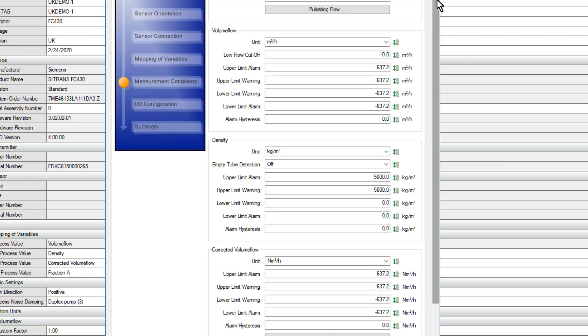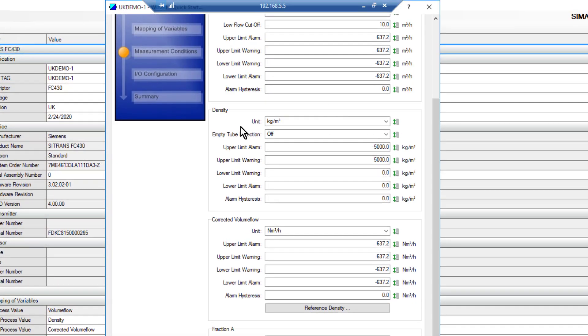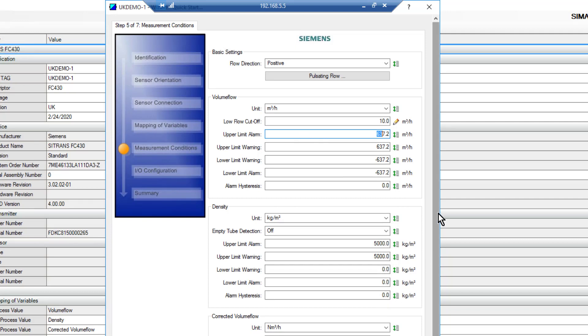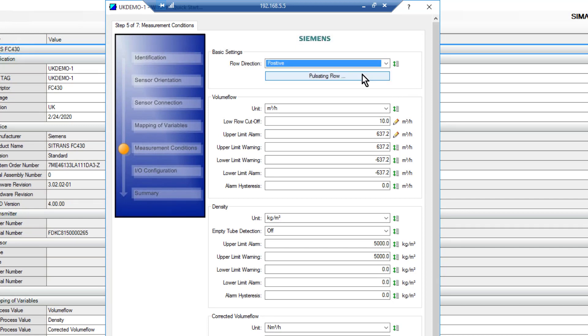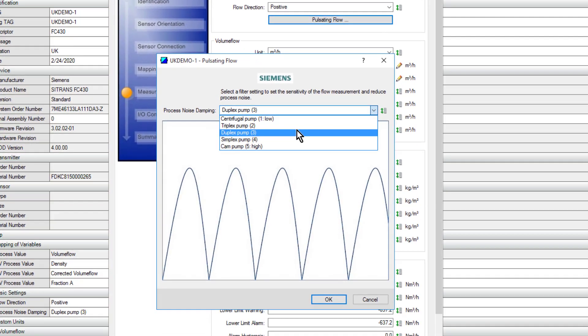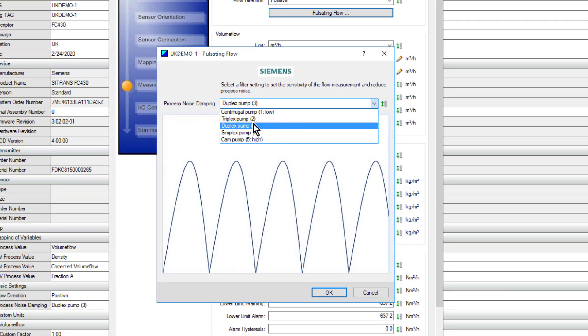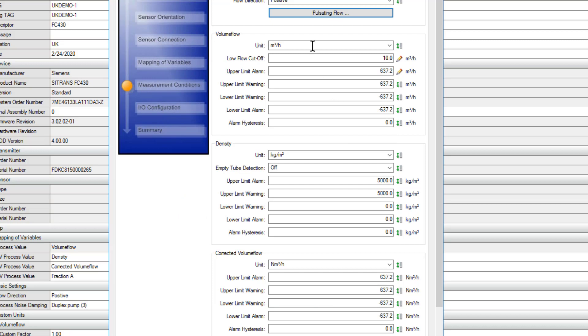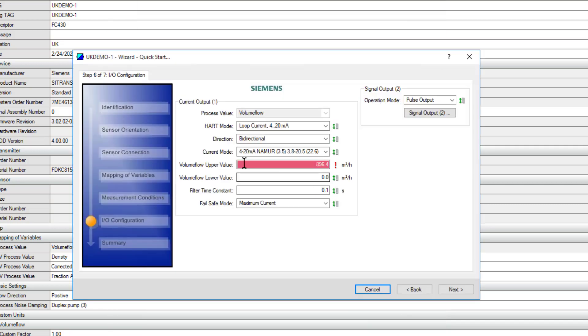What we have here are our process values. The first process value is your HART memory map, but the first one is also your milliamp output on milliamp output one. This next screen looks a bit busy because it is a multivariable flow meter. What we need to be concerned about is the low flow cutoff. These are just software alarms for each of the measurements, which we're not really concerned about. Then we have forward or negative flow if somebody has put the flow meter in the wrong way around, and pulsation settings. Normally if you don't know, leave it on three, the middle one. Depending on the application, if you're doing high-speed batching, it might need to go on faster option.